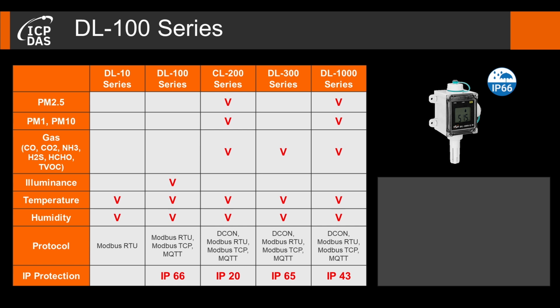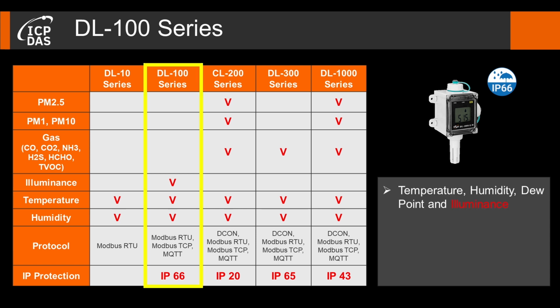The DL-100 series remote temperature and humidity data logger can also measure the temperature and humidity and dew point. However, compared to the DL-10 series, the L100 series can also measure the illuminance and support Modbus TCP and MQTT protocols. In addition, the L100 series features a built-in data logger that records measured information on temperature, humidity, and dew point, along with corresponding dates and timestamps. The data is then saved as CSV files for future review and analysis.